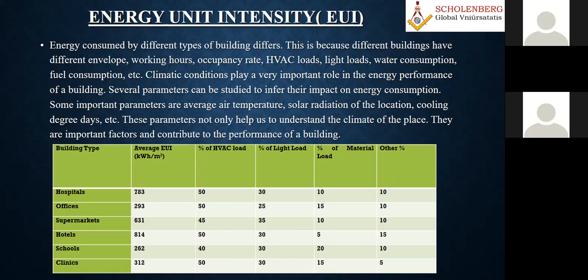On that basis, every building has a different envelope and different working hours. We have occupancy rates and different kinds of HVAC loads, and different kinds of light loads. Then, of course, water consumption and fuel consumption. So for that purpose, normally they try to have a benchmark called the energy unit intensity. Its unit is kilowatt hour per meter squared.